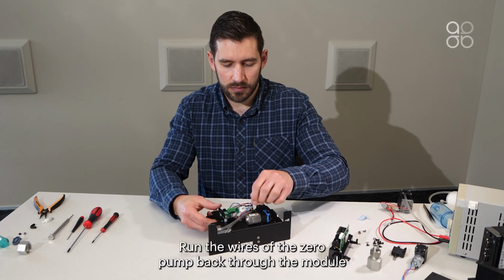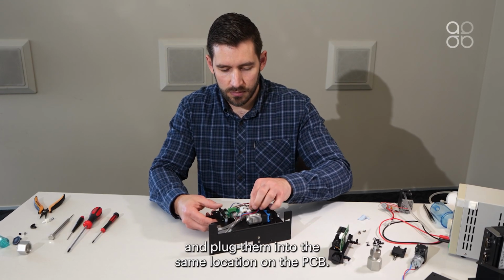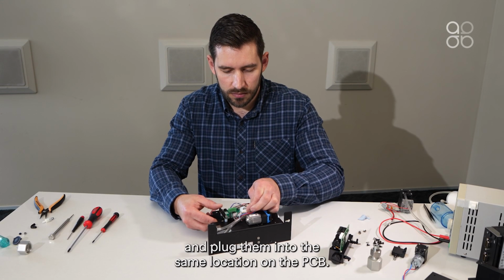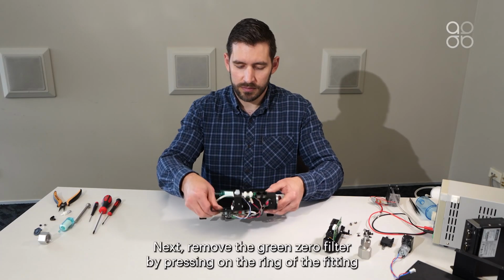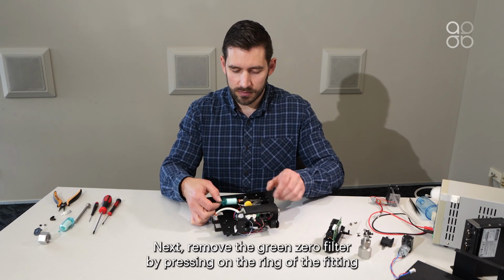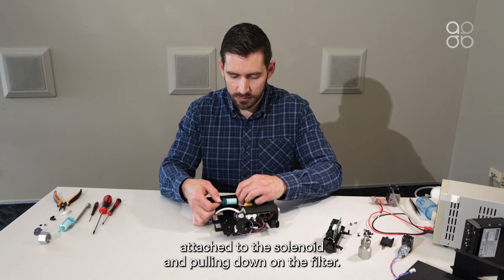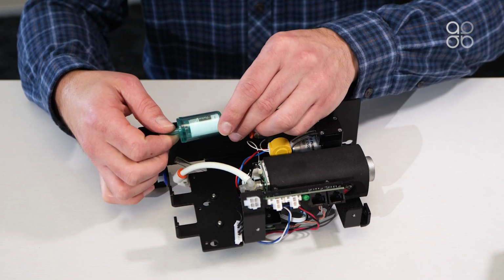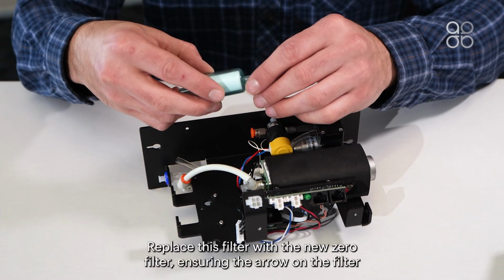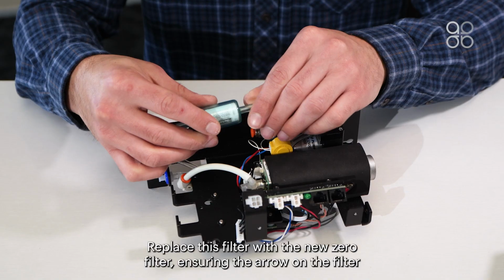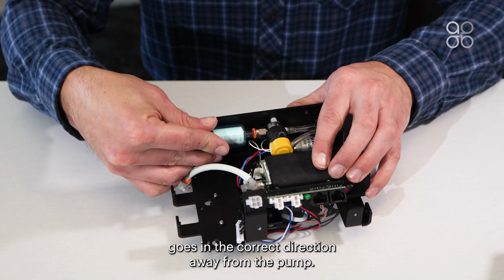Run the wires of the zero pump back through the module and plug them into the same location on the PCB. Next, remove the green zero filter by pressing on the ring of the fitting attached to the solenoid and pulling down on the filter. Replace this filter with the new zero filter, ensuring the arrow on the filter goes in the correct direction, away from the pump.